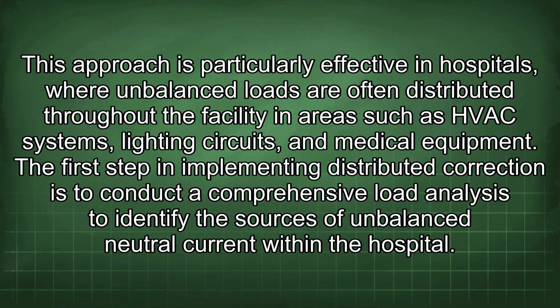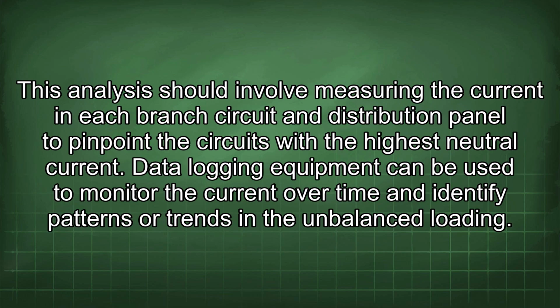This approach is particularly effective in hospitals, where unbalanced loads are often distributed throughout the facility in areas such as HVAC systems, lighting circuits, and medical equipment. The first step in implementing distributed correction is to conduct a comprehensive load analysis to identify the sources of unbalanced neutral current within the hospital. This analysis should involve measuring the current in each branch circuit and distribution panel to pinpoint the circuits with the highest neutral current.